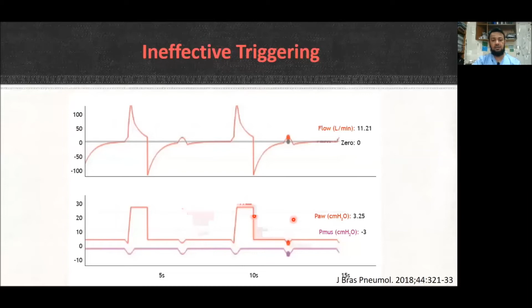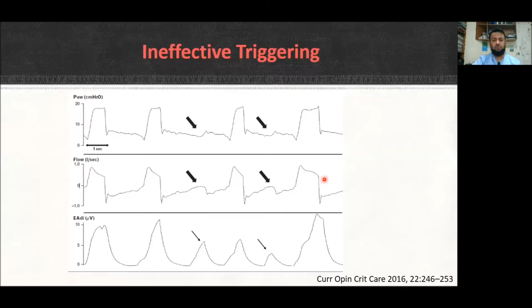This is another example. This is a pressure waveform and this is a flow waveform, and this is the electrical activity of the diaphragm. So here the diaphragm is moving and the ventilator is detecting and a respiration is delivered, but here maybe diaphragmatic activity is low, that's why some negativity is there, but the ventilator could not detect that negativity, so no respiration was delivered. So this is another example of trigger asynchrony. Here again no respiration was delivered, though the patient tried to take a respiration; there was mild positivity, but maybe trigger sensitivity was inappropriate. So we have to set the trigger sensitivity appropriately.